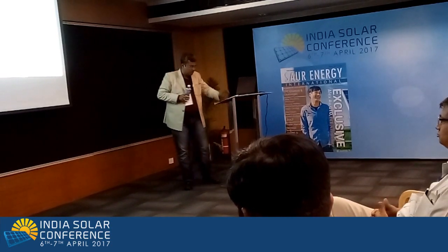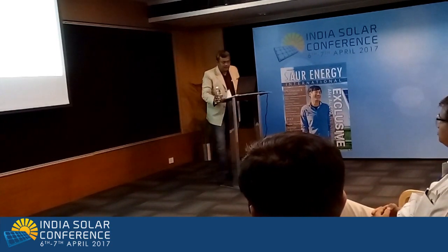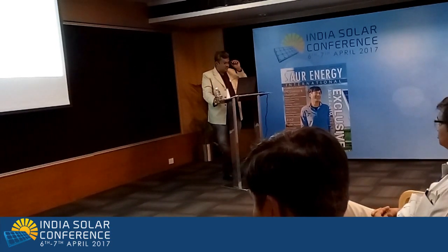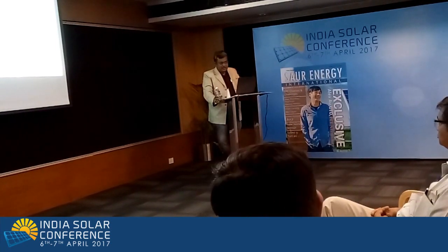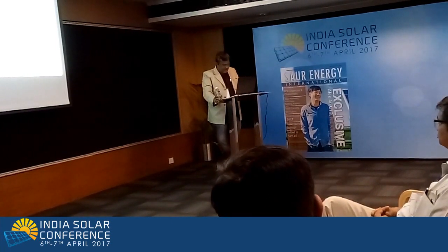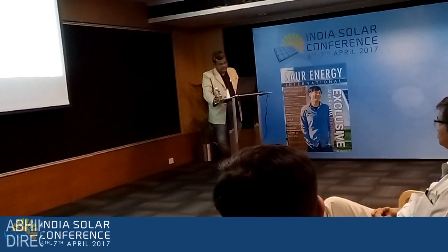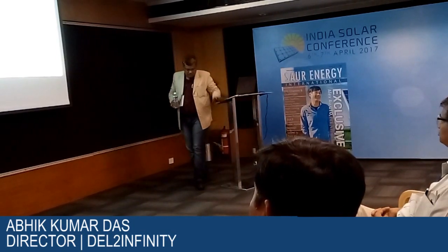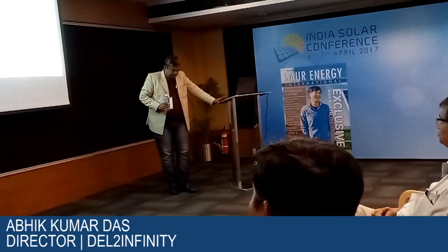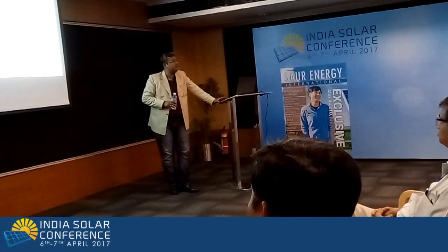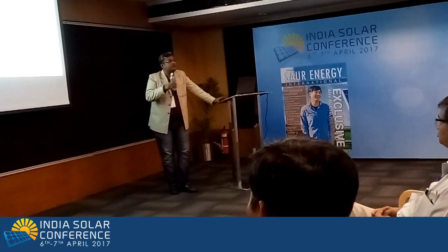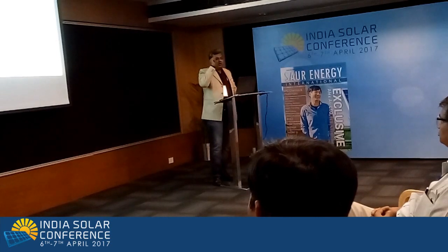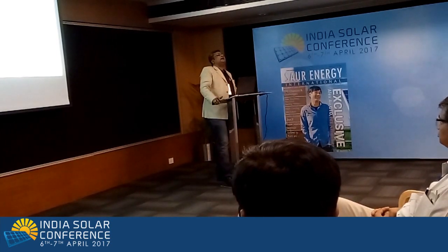So basically one data point is how many kilowatt hours in 15 minutes, or you can say the average power in these 15 minutes. So the forecast horizon for 1 hour is 4 time blocks, day ahead is 96 time blocks, weekly is 672 time blocks, and monthly is 2880 time blocks. So when calculating the total monthly penalty, the SLDC will calculate over 2880 time blocks what your plus minus is, and whether your forecast is within the no penalty zone or beyond it, and they will calculate the total penalty and produce a bill every 3 months.